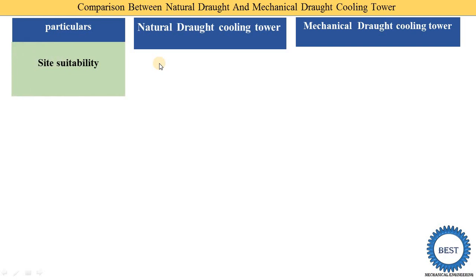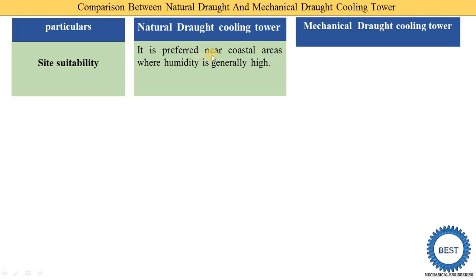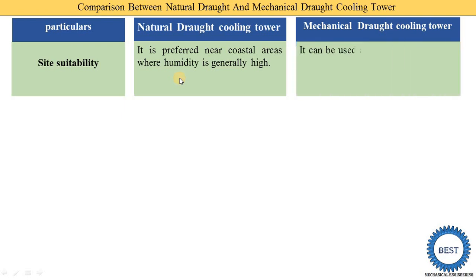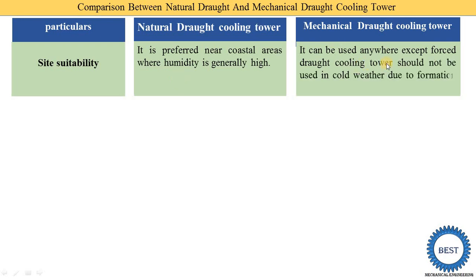The next difference is site suitability — at which location we can use natural draft or mechanical draft cooling towers. Natural draft cooling towers are suitable and preferred near coastal areas where humidity is generally high. Mechanical draft cooling towers can be used almost anywhere, except forced draft cooling towers should not be used in cold weather conditions due to the formation of ice on the blades of the fan.